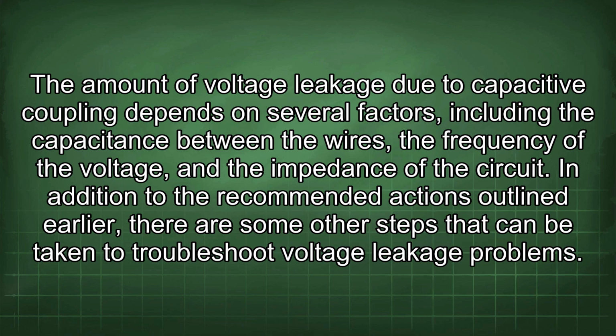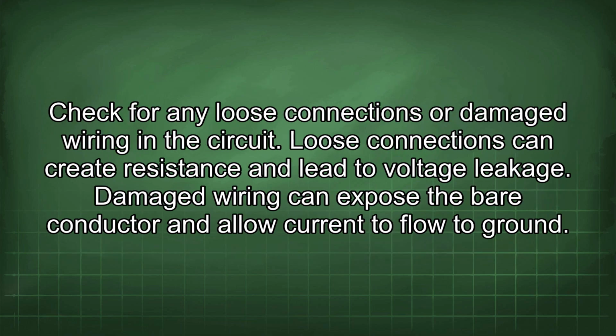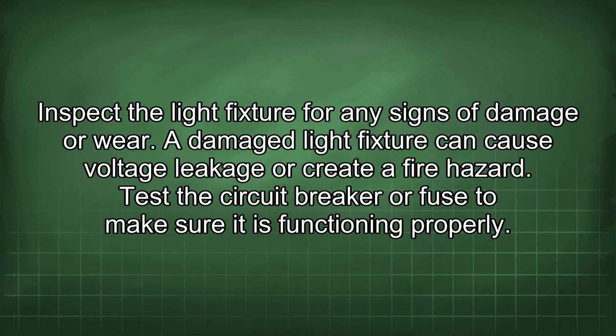In addition to the recommended actions outlined earlier, there are some other steps that can be taken to troubleshoot voltage leakage problems. Check for any loose connections or damaged wiring in the circuit. Loose connections can create resistance and lead to voltage leakage. Damaged wiring can expose the bare conductor and allow current to flow to ground. Inspect the light fixture for any signs of damage or wear. A damaged light fixture can cause voltage leakage or create a fire hazard.